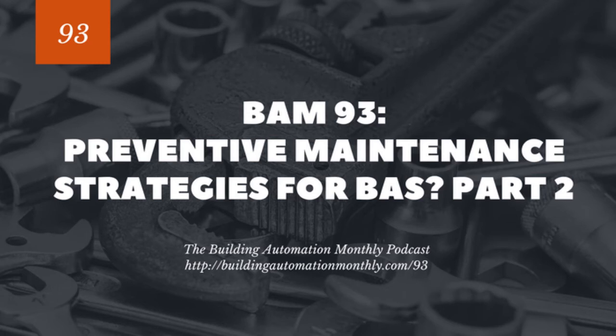Next up, we have sequence verification. Now, sequence verification is something that should be done quite often, and here's why. The HVAC guys go and do some maintenance on an air handler, and they change some stuff around. Maybe they change the drive settings for whatever reason, or maybe they take an actuator off while they're working on something and they leave it off.